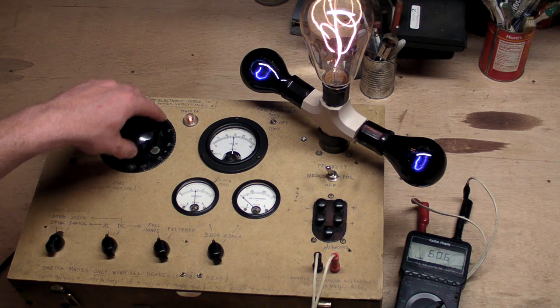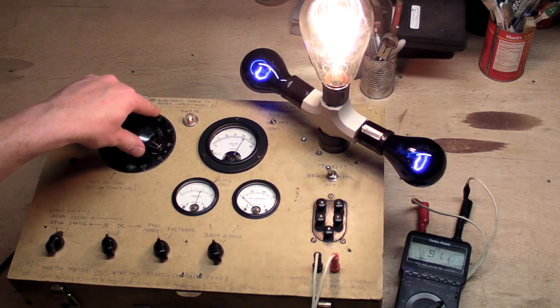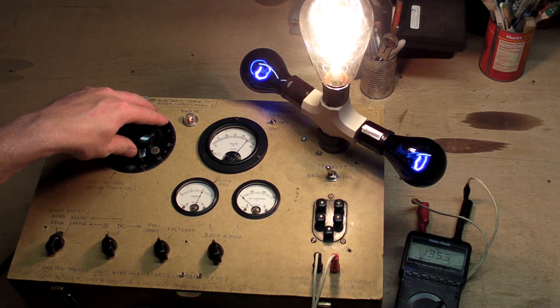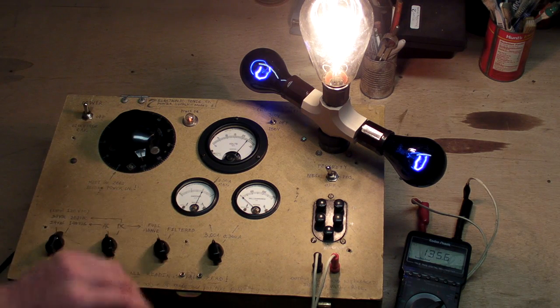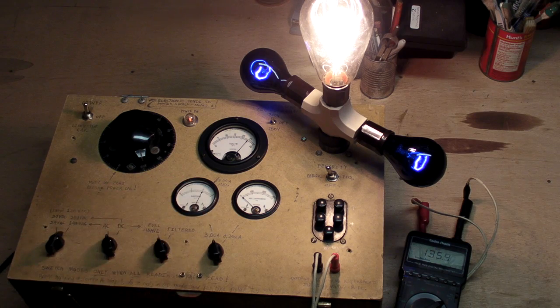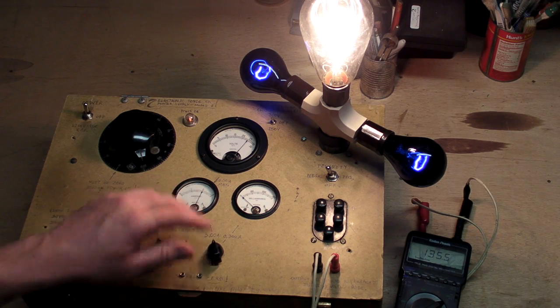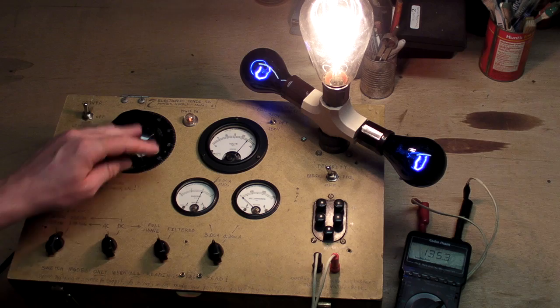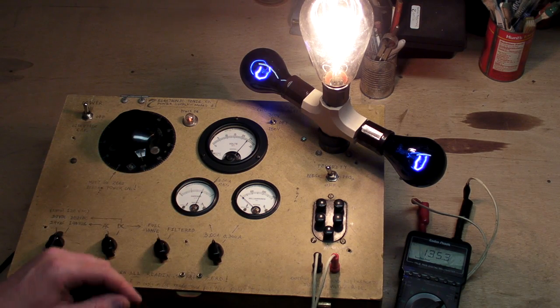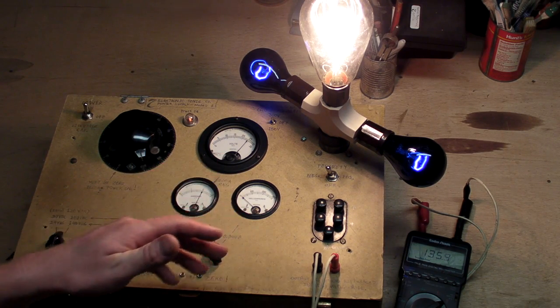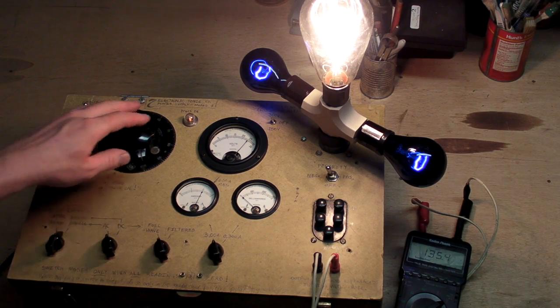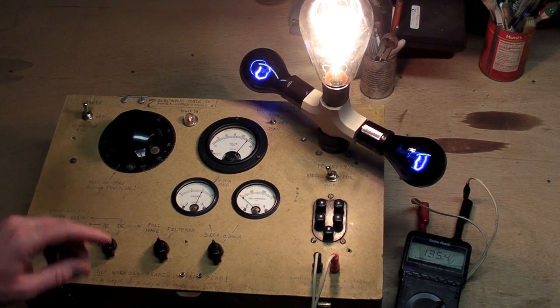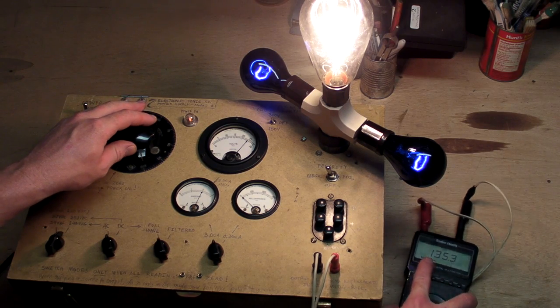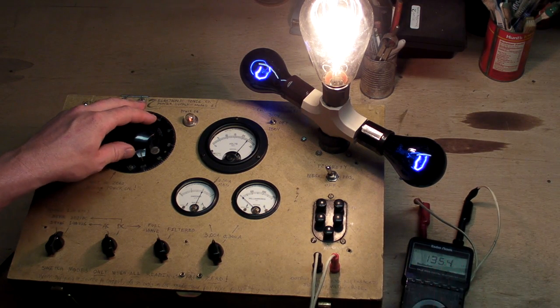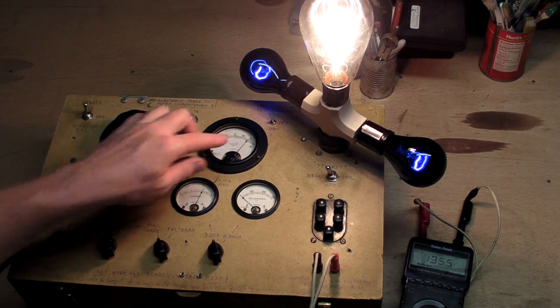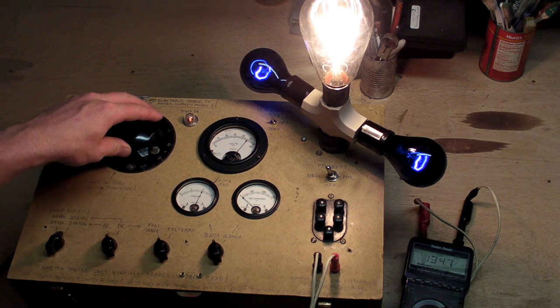Let me turn that on, put it on the 140 volt scale, crank it up, and you can see the current here. We're going to get to about 2 amps. Again, the current isn't very accurate, it'll be plus or minus 100 or 200 milliamps or so, because of the rectifier situation and the fact I'm trying to measure AC current on a DC meter. But it's close enough. I got 135 volts on the DMM, whereas this one is only showing about 120.